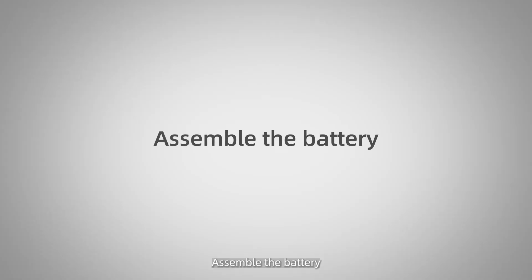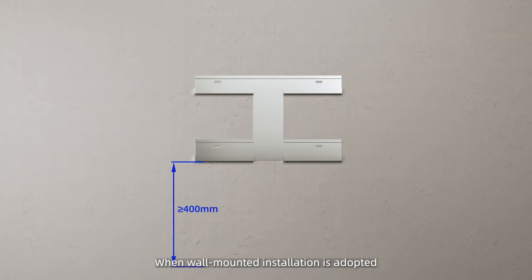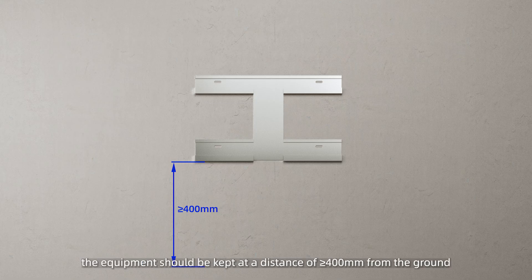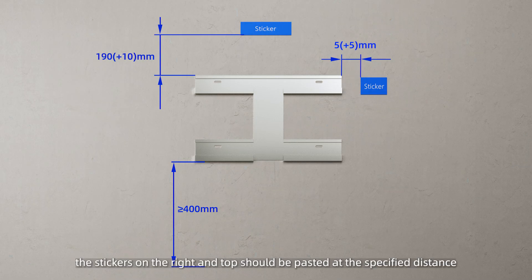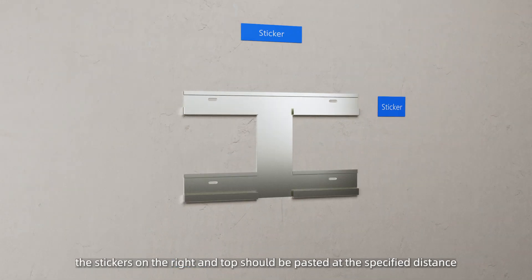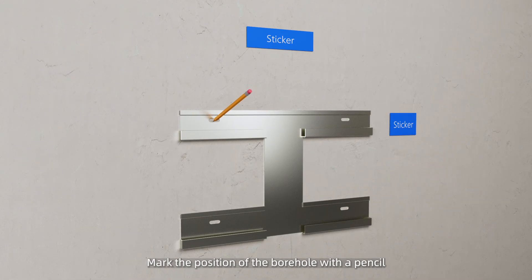Assemble the battery. When wall-mounted installation is adopted, the equipment should be kept at a distance of greater than or equal to 400mm from the ground. After fixing the wall bracket, the stickers on the right and top should be pasted at the specified distance. Mark the position of the borehole with the pencil.